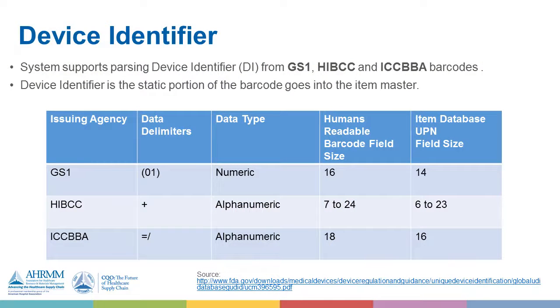The three accrediting bodies recognized by the FDA are: GS1, or Global Standards 1, which has a standardized 14-character barcode. It is recognized with '01' in parentheses at the beginning — if you see a string of numbers with '01' in front, that's your GS1 barcode, and that's what we want to capture in your item master. The HIBCC, or Healthcare Industry Business Communications Council — typically written H-I-B-C-C, and we call it HIBCC — starts with a plus sign and typically an alpha character, followed by a string of alphanumeric characters from 6 to 23 characters in length. So there is no standardized length, but the longest character field you'll need in your item master is 23 to hold your HIBCC barcodes.